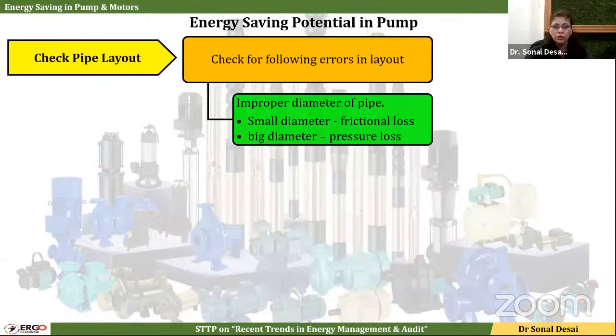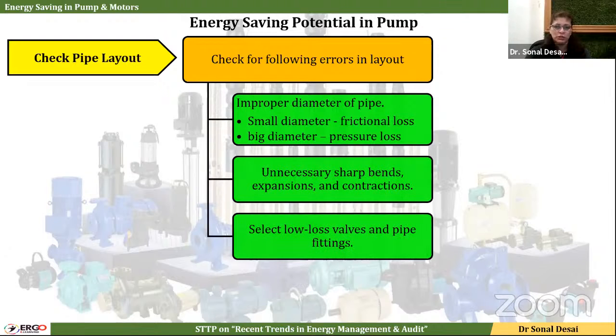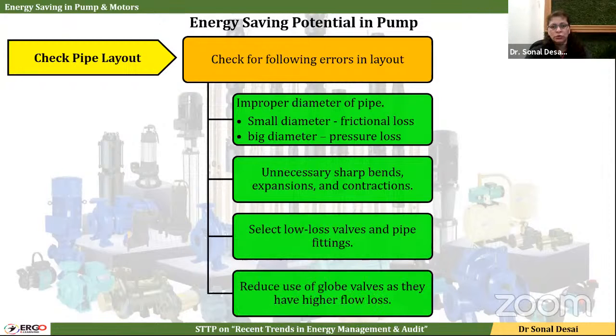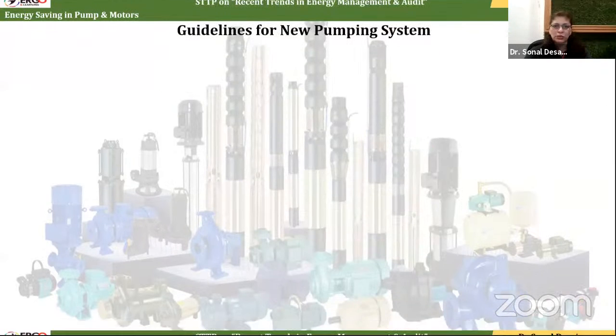Check the pipe layout. It should not be too big, as it will create pressure loss. It should not be too small, otherwise it will create frictional loss. There should not be undue, unnecessary sharp bends, expansions, and contractions, so that will also create friction. Select low loss valves and pipe fittings. Don't go with globe valves. It is also bad to have more flow losses.